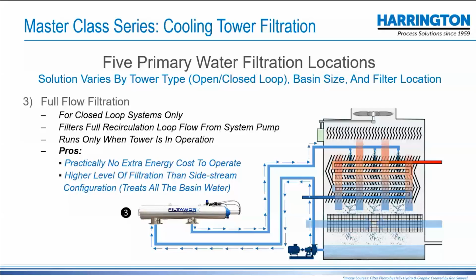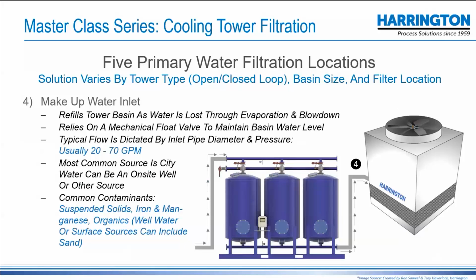City water is notorious for having at times high levels of iron and manganese, sometimes organics and biofilm. Iron and manganese would be a concern because, of course, that will cause a buildup on equipment. And it might be necessary to treat that. Really, the only practical way to treat that would be with a media filter. Perhaps some cartridge filters could help, but media filter would be more typical.